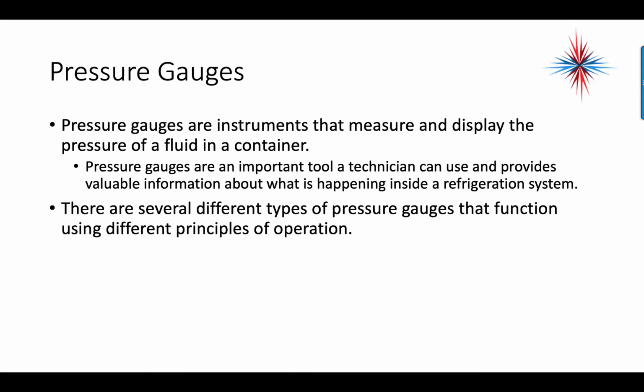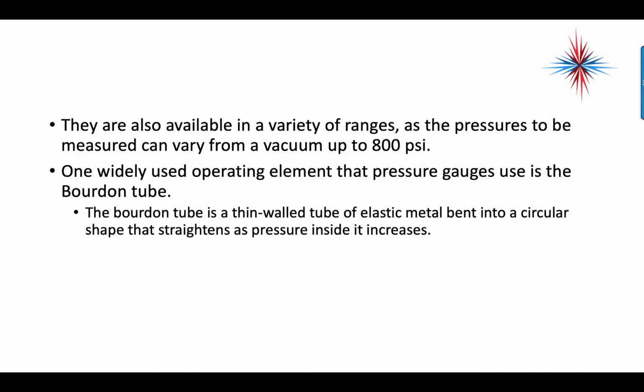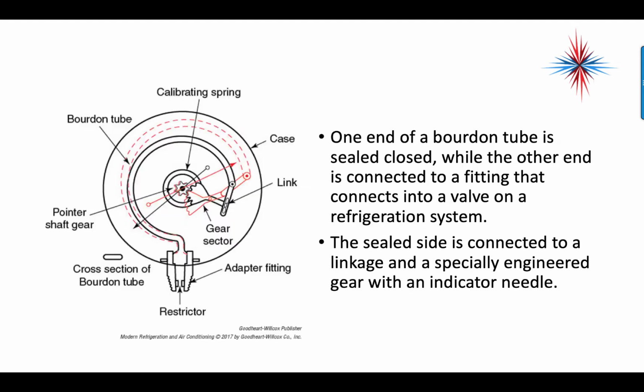There are several different types of pressure gauges that function using different principles of operation. They also are available in a wide variety of ranges, as the pressures measured can vary from a vacuum, which is a negative pressure, up to 800 psi or higher. One widely used operating element that pressure gauges use is the Bourdon tube. The Bourdon tube is a thin-walled tube of elastic metal that is bent into a circular shape that straightens as the pressure inside of it increases.